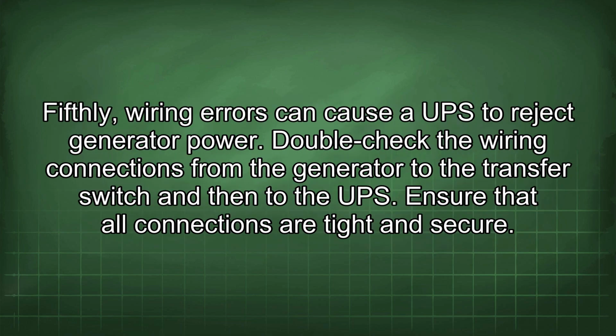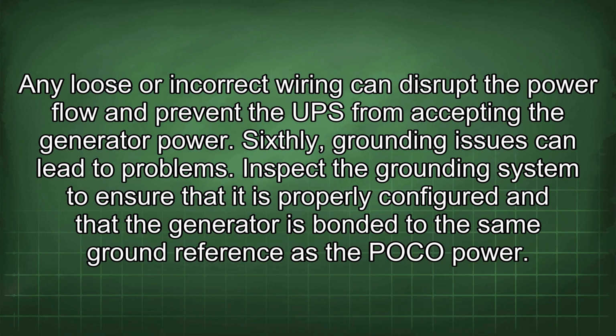Fifthly, wiring errors can cause the UPS to reject generator power. Double-check the wiring connections from the generator to the transfer switch and then to the UPS. Ensure that all connections are tight and secure. Any loose or incorrect wiring can disrupt the power flow and prevent the UPS from accepting the generator power.